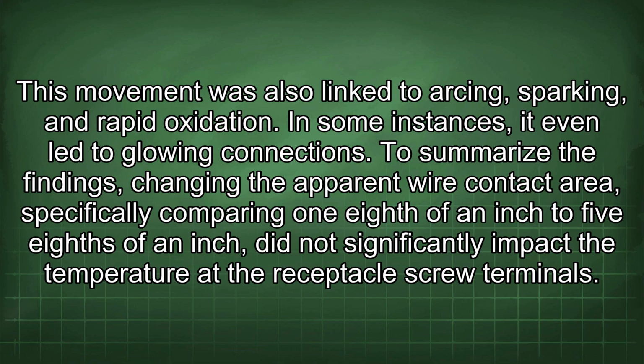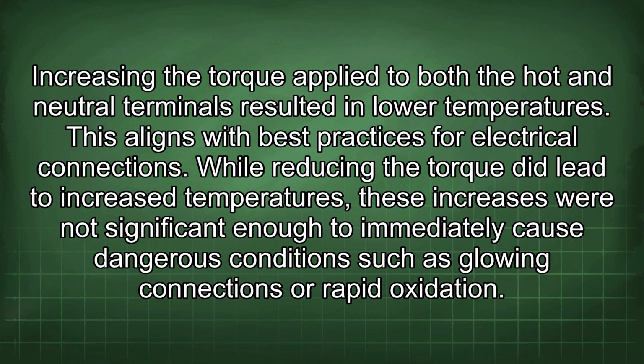To summarize the findings, changing the apparent wire contact area, specifically comparing 1/8 of an inch to 5/8 of an inch, did not significantly impact the temperature at the receptacle screw terminals. Increasing the torque applied to both the hot and neutral terminals resulted in lower temperatures. This aligns with best practices for electrical connections. While reducing the torque did lead to increased temperatures, these increases were not significant enough to immediately cause dangerous conditions such as glowing connections or rapid oxidation.